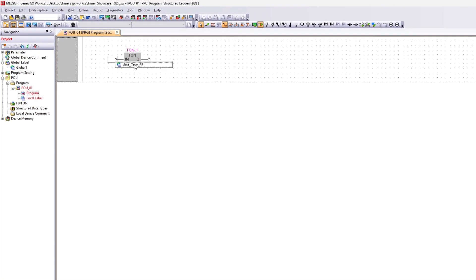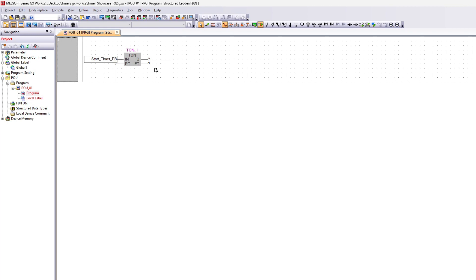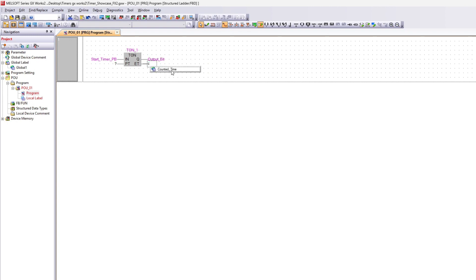The input is a bit tag that will start the timer. Q output is a bit tag that will go high once the preset value is reached. ET stands for elapsed time and is how much the timer has counted up. PT is preset time — it tells how much we will count up to. It can be declared as seconds, minutes, milliseconds, or whichever you like.